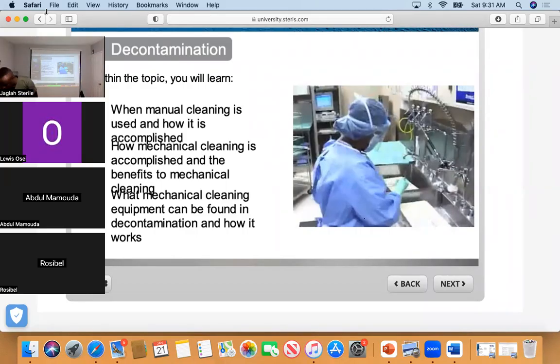You also have to understand that after your manual cleaning is done, your instrumentation should be handled without any fear of infection, right? Because you have disinfected the instrumentation. So the person in prep and pack will not put on PPE to handle the instrumentation that is coming in. All right, I hope I'm not confusing you, but this is important. We are dealing with stainless steel or metal instrumentation. Now, this looks like stainless steel or metal, but this is a camera. Don't put a camera inside a washer. This can be soaked because there's nothing on here that will break if it goes inside water. Okay, but certain equipment, like battery-powered equipment, if you soak it, these are pieces of equipment that cannot be submerged.